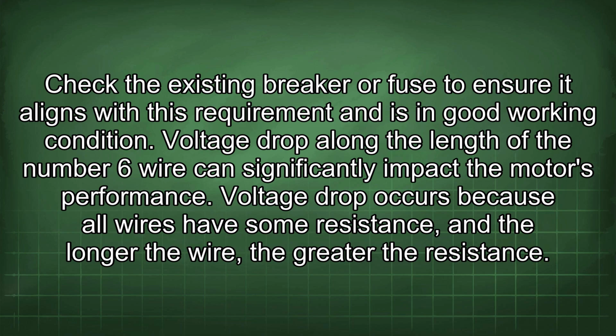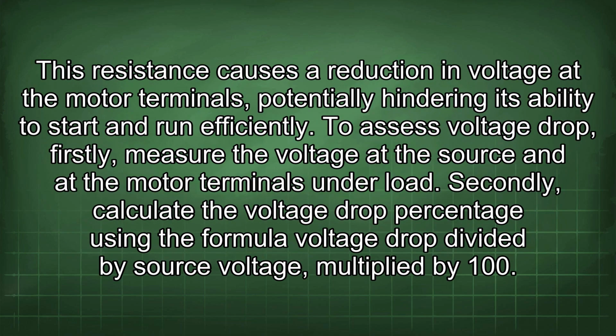Voltage drop along the length of the number 6 wire can significantly impact the motor's performance. Voltage drop occurs because all wires have some resistance, and the longer the wire, the greater the resistance. This resistance causes a reduction in voltage at the motor terminals, potentially hindering its ability to start and run efficiently.